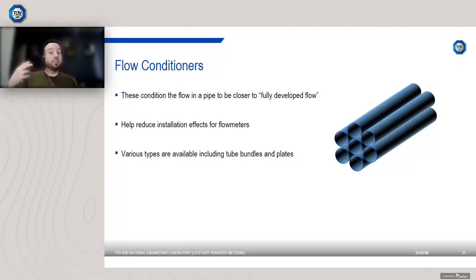So these essentially help reduce installation effects, and you get various different types, including tube bundles, which is kind of the image shown here. You get perforated plates, honeycomb structures. They're all doing the same thing, but the key thing to obviously note is they will introduce a pressure drop into the flow stream. And if that's a big consideration, you might then want to select a technology like Coriolis or positive displacement, which is not affected by installation effects. So again, it depends on the metering technology if you need to implement a flow conditioner.